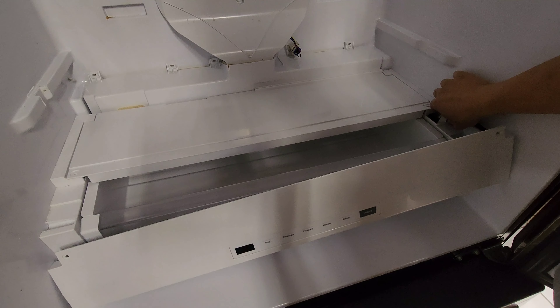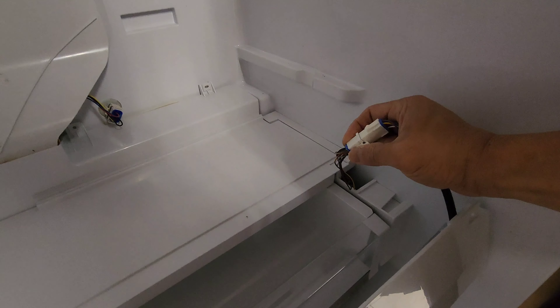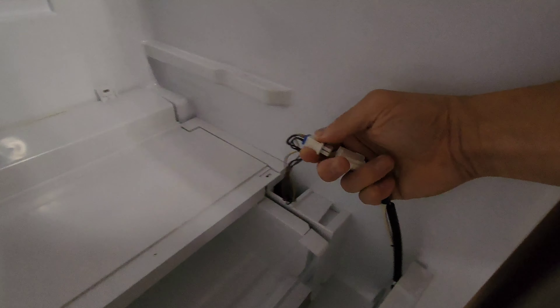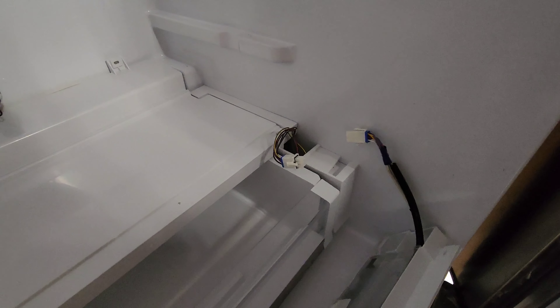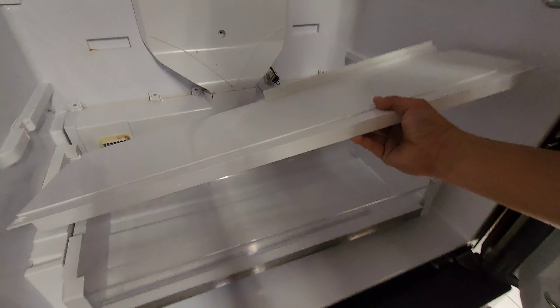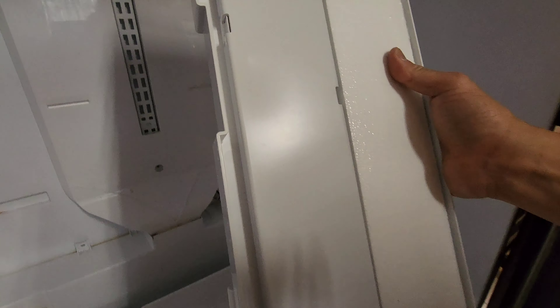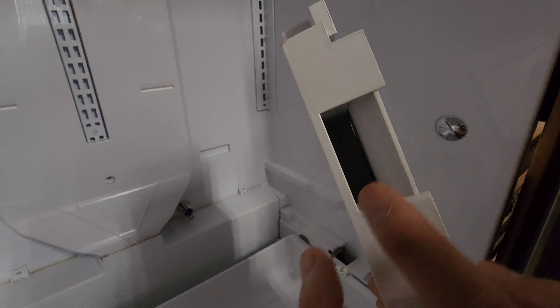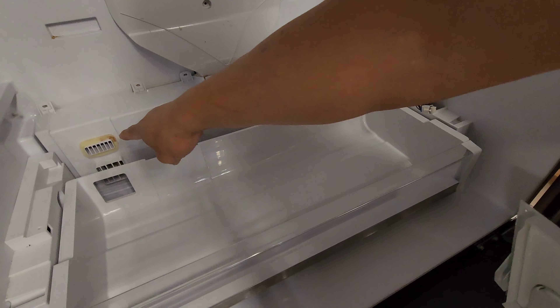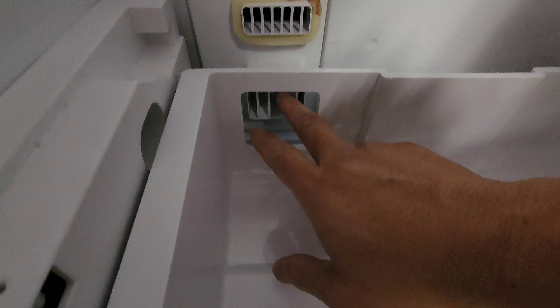The electrical connection is here, so let's get it removed. Push down and pull apart. I'll remove this cover. There's a channel here, and another channel here — air intake and exhaust here to keep this compartment cold. There's a fan over here: exhaust and the return — air return. So the air comes in, goes to the top plate, circulates, and goes back.